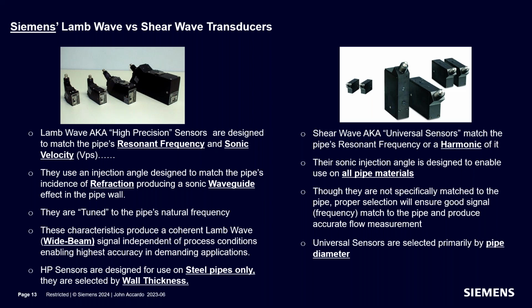And interestingly, what you might not know, or maybe you do know, high precision sensors can't be used on plastic pipes. And the reason for that is you don't get the resonance. You don't get resonance and you don't get the Lamb wave travel in a plastic pipe that you do on a metallic pipe. So you can't, in fact, use high precision transducers on a plastic pipe. Even though they're not specifically matched to the pipe, proper selection of the universal transducers will ensure the best quality signal and match to the pipe that you're trying to measure and produce an accurate flow measurement.